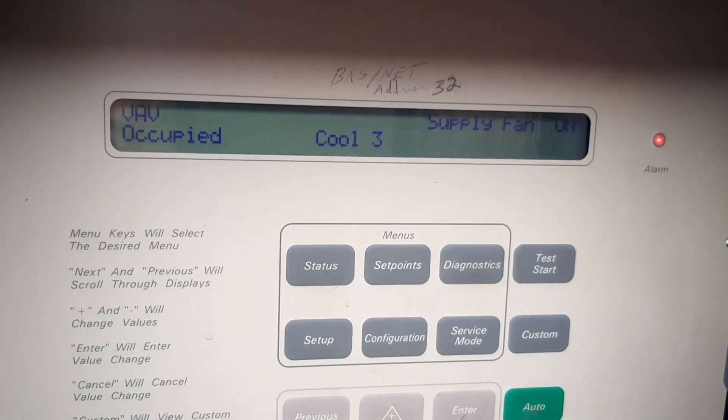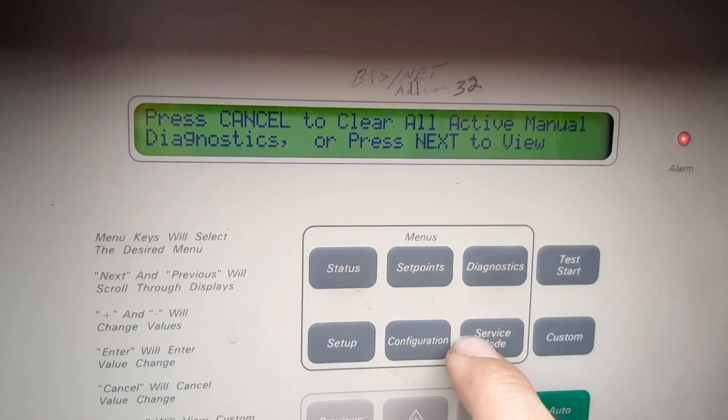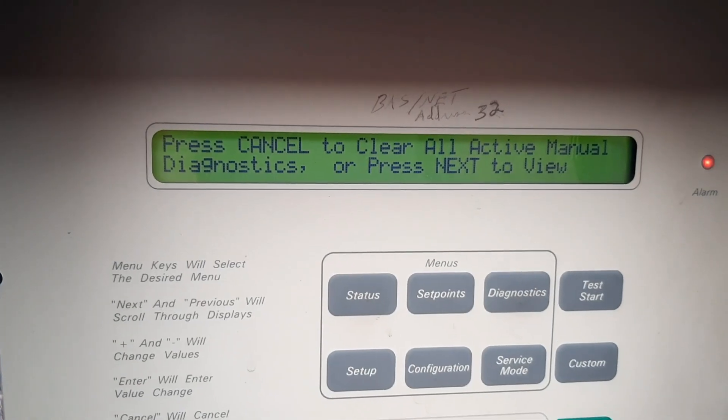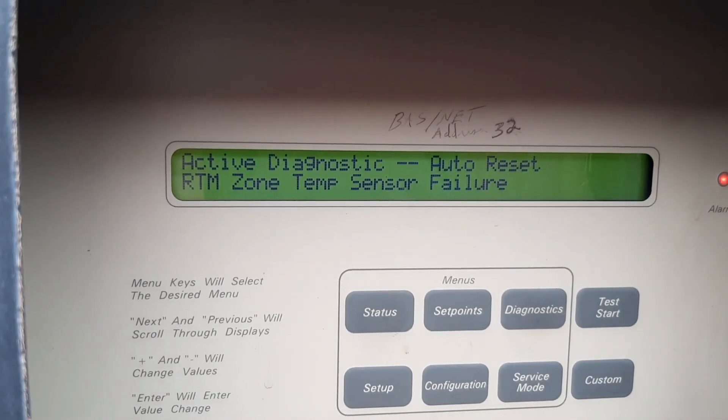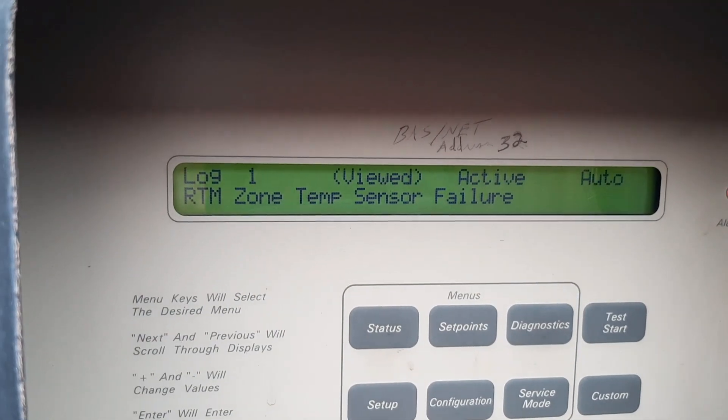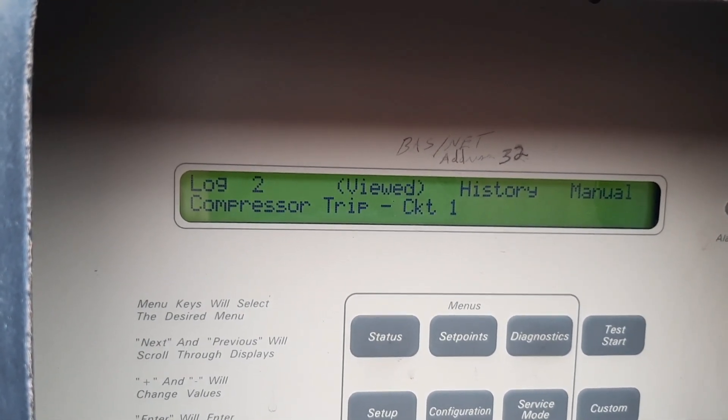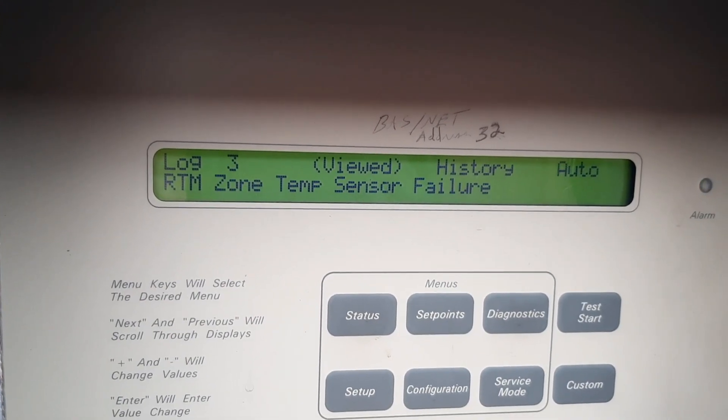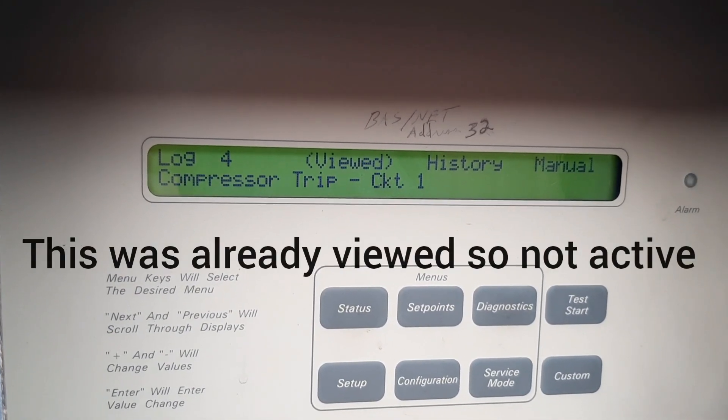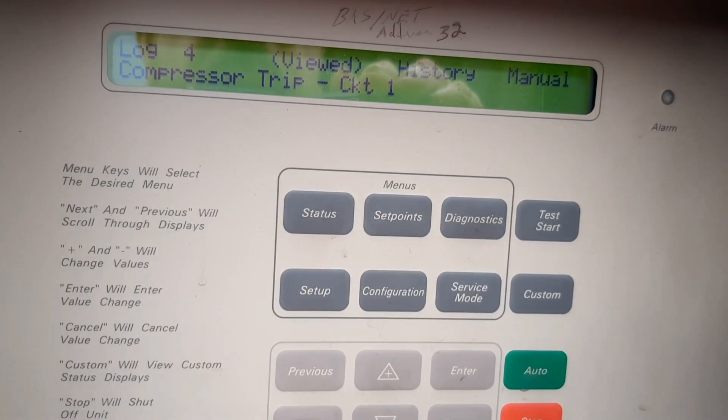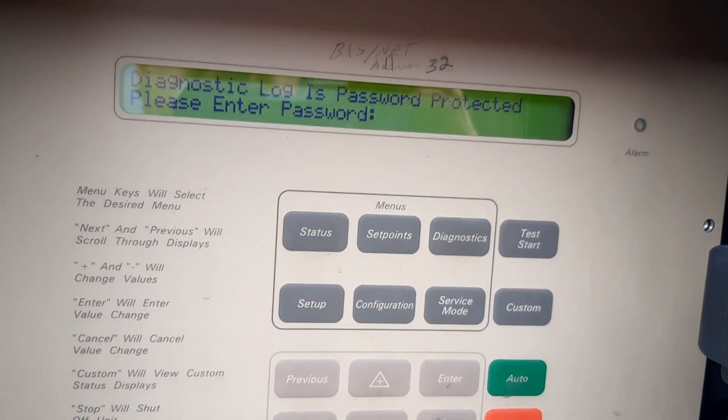So we do have some kind of diagnostic. Let's see, zone temp failure, that's typical. Compressor trip circuit one. Alright, so we got a compressor trip.